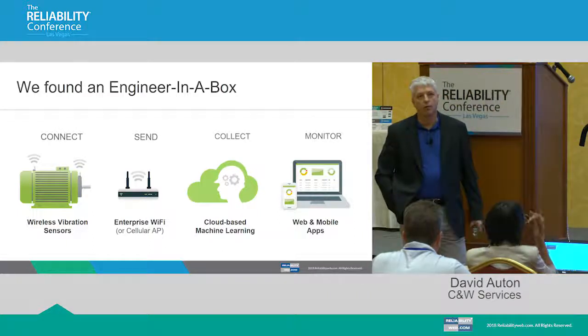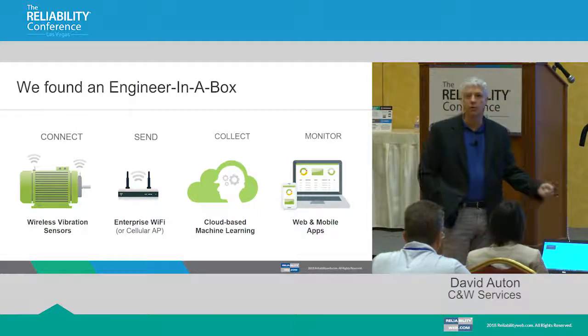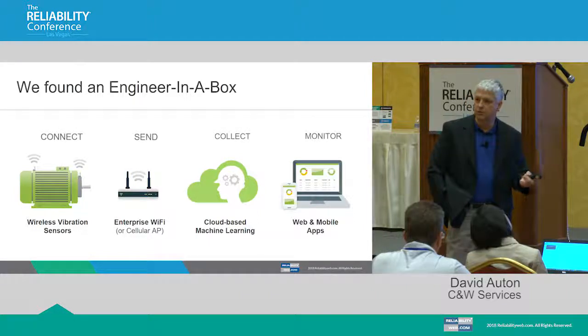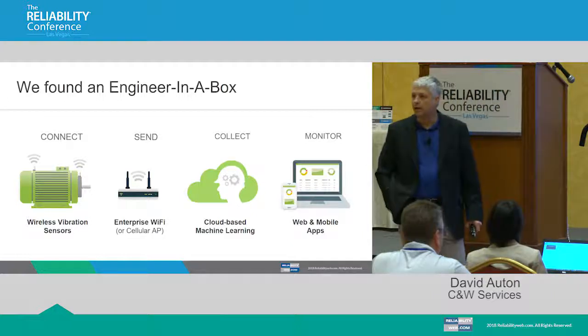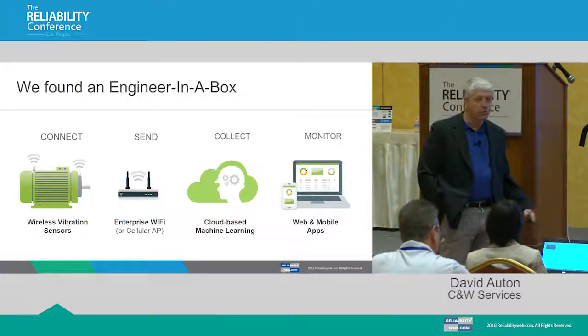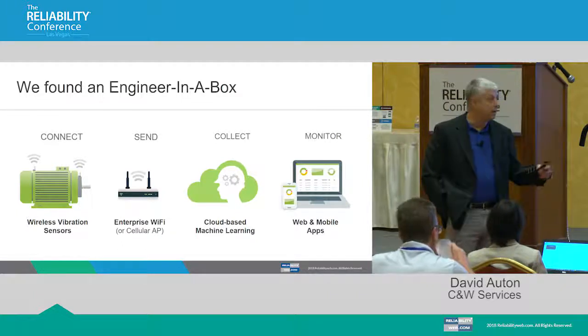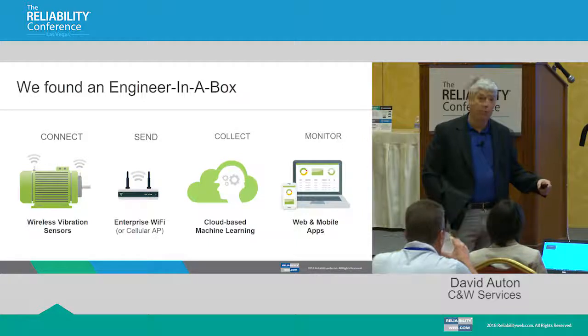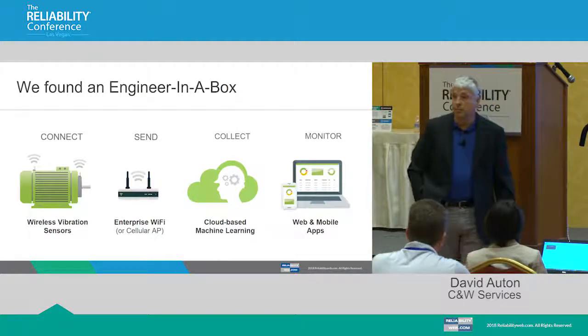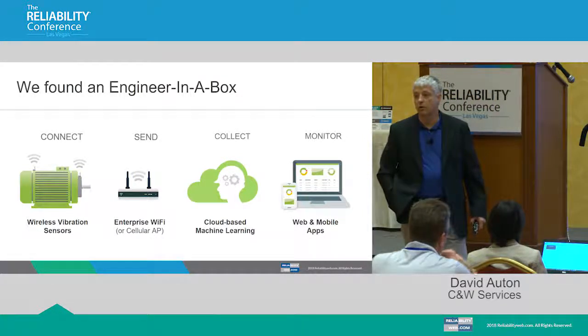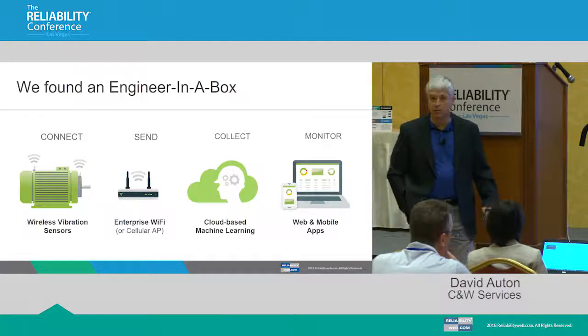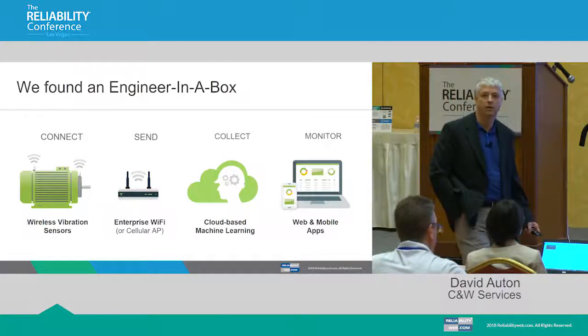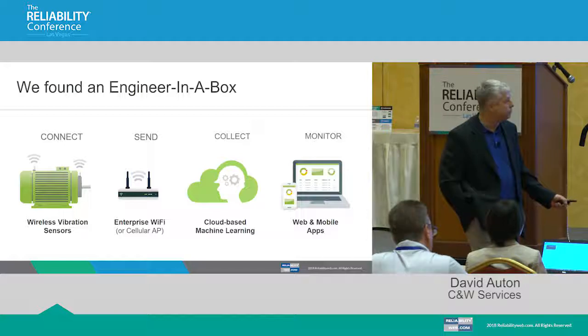The other piece is, can I get to this with my common technology? I think the holy grail we're trying to get to is one screen for our building automation systems, our control engineers, our fault diagnostic systems - this just becomes another attribute to that. My air handling is low. Why? Well, my BAS alarm is showing this, my airflow meters are showing this, and oh wait a minute, now I'm looking at my actual air handling unit, and there's a large vibration and the temperature's going up on the main bearing or something. Then you kind of know what's going on. So it really adds to that.